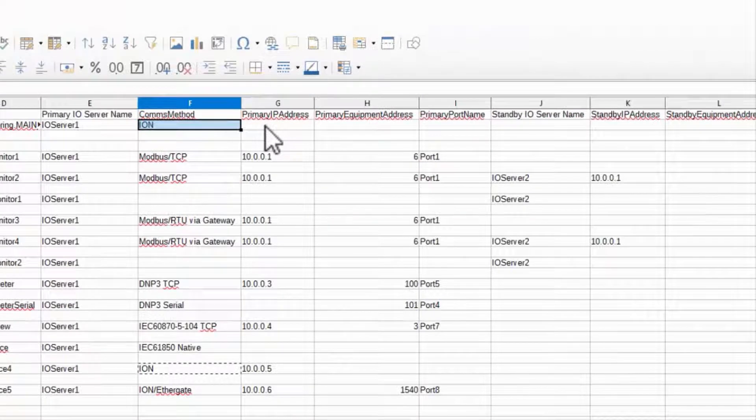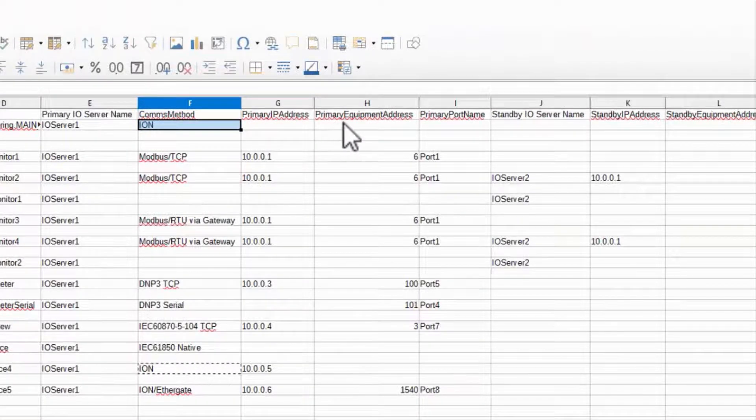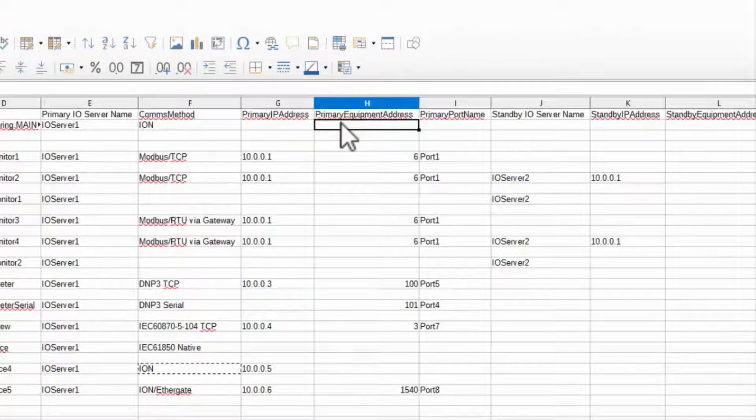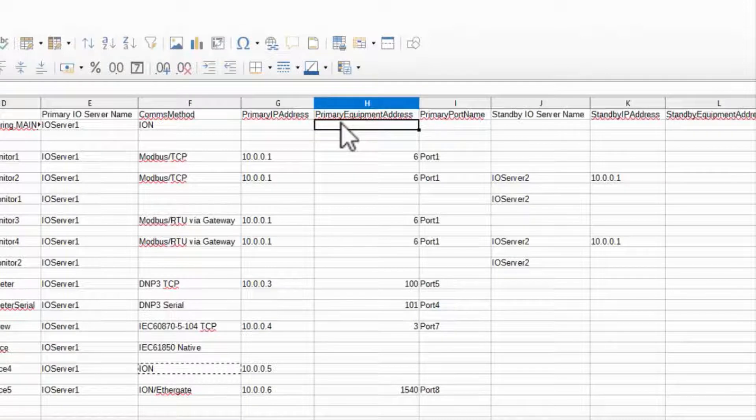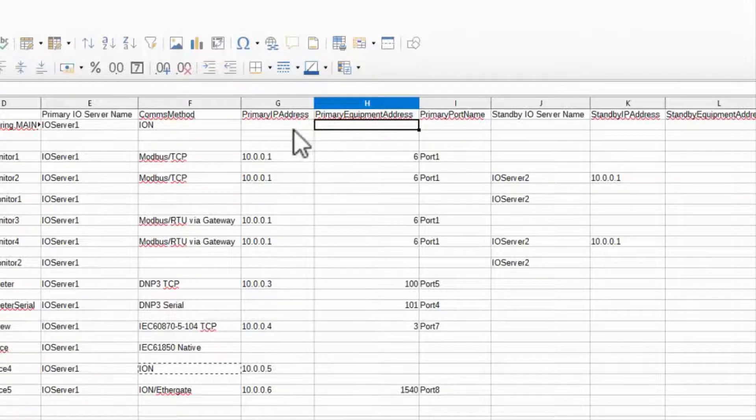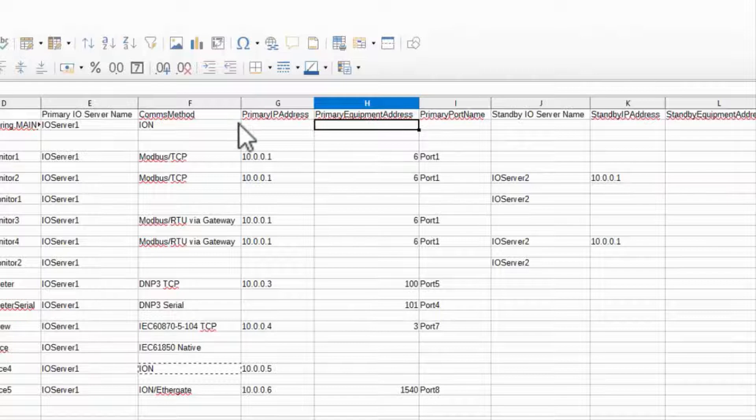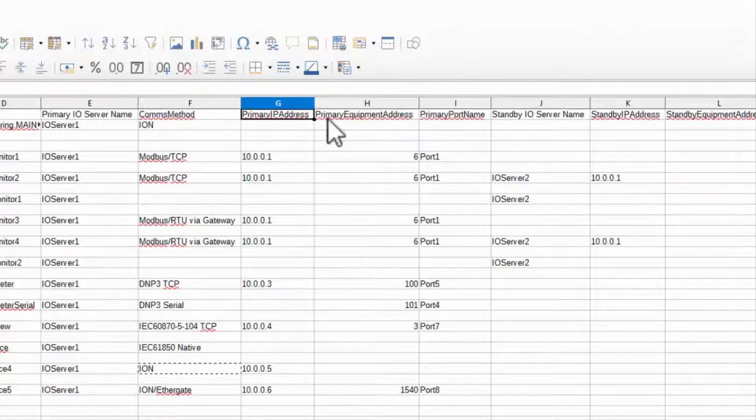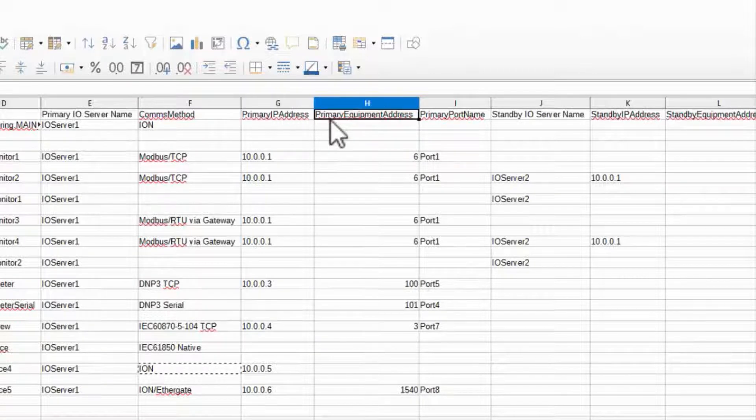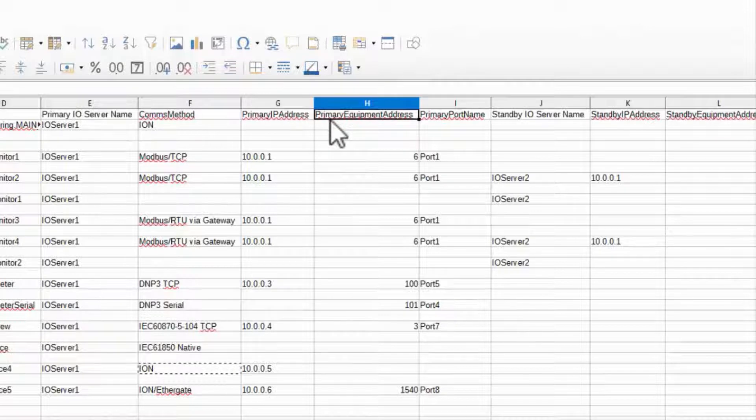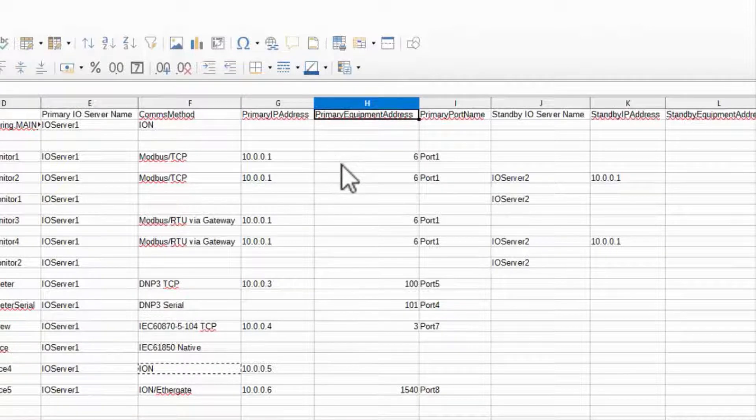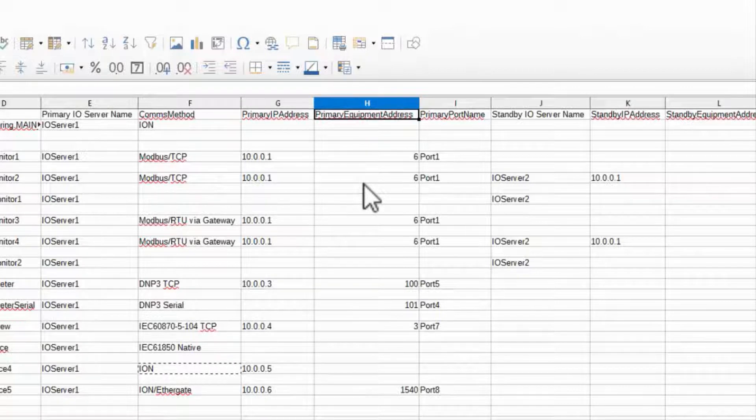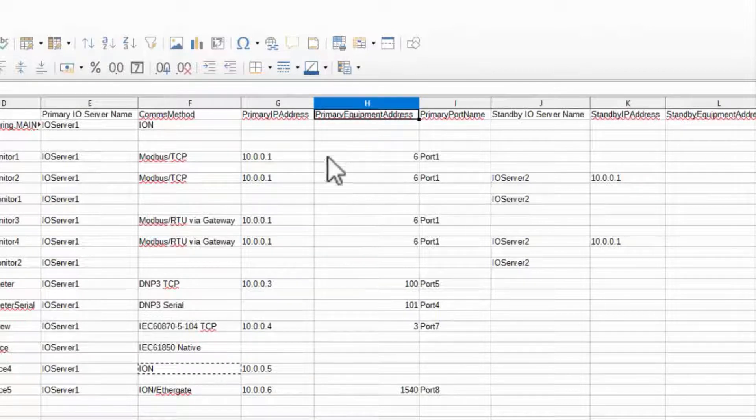Primary IP address and primary equipment address are my ethernet and serial addresses, respectively. Since my Ion device communicates over ethernet, I can skip the equipment address, but note that Modbus TCP devices still require that serial address. If you don't know what it is for them, you can use 255.